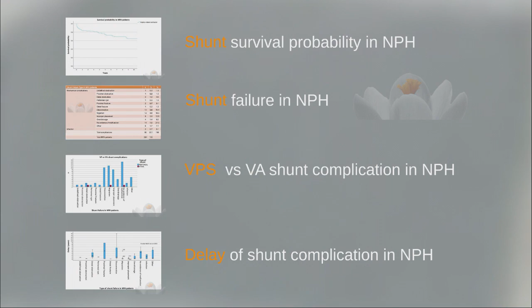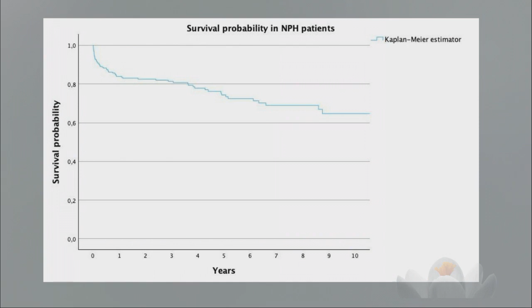If we look at the probability of shunt dysfunction using double pin Sophysa devices, it's higher during the first years, with a rate estimated at 16% using a Kaplan-Meier estimator. If we regard the shunt failure type, and especially the mechanical complications, they are represented by disconnection and disconnection plus migration in 7.5%, which represents more than 40% of all the complications.